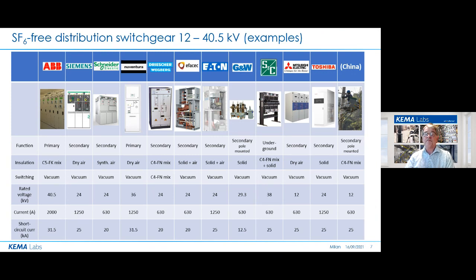Then let's have a look at the medium voltage distribution switchgear. Looking at this chart, the vast majority is with vacuum interrupters. Some designs are not new, since some companies banned SF6 a long time ago. Combining atmospheric dry air with field control shields and some solid makes it possible to reduce the size of 24 kV ring main units to that of SF6 insulated ones.